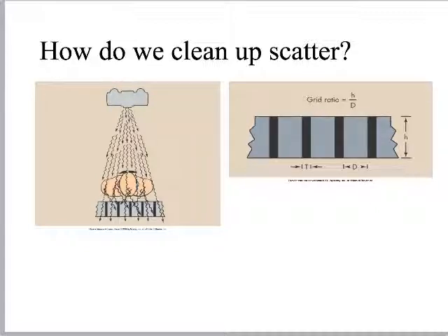So as a general rule of thumb, if we're on portables, we should not use a grid higher than a 6x1 grid. So you'll notice most of your grids, if you were working on a portable machine, are 5x1, 6x1 max for any kind of stationary grid, something that's not a Bucky, that doesn't vibrate as you're taking an image. So for stationary grids, 6x1 is the maximum.